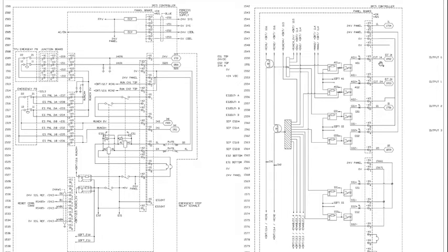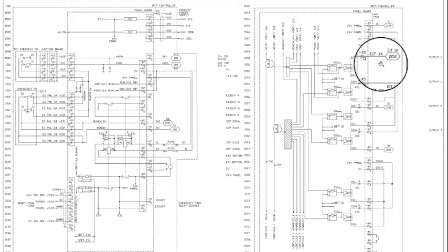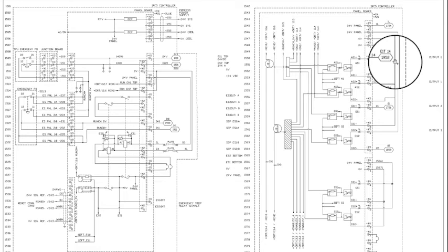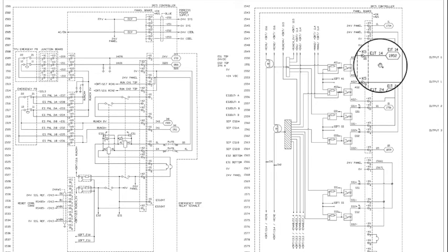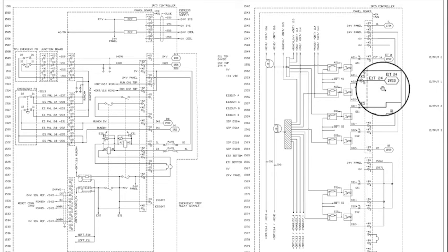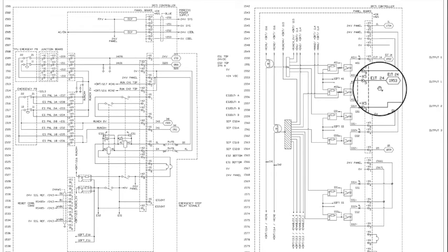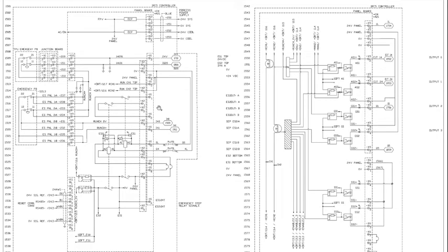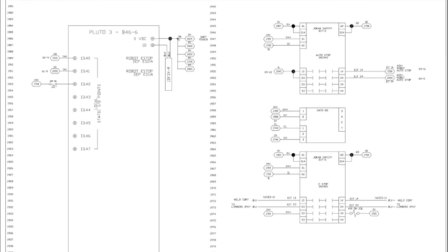The first step that needs to happen is for the electrician to understand what type of field device is being connected into the auto stop chain. Some devices may require seeing each channels positive side and some devices may require a mixture of positive and negative. In the example I am showing we are using both AS1 positive and AS2 positive to satisfy Jokab safety relay.